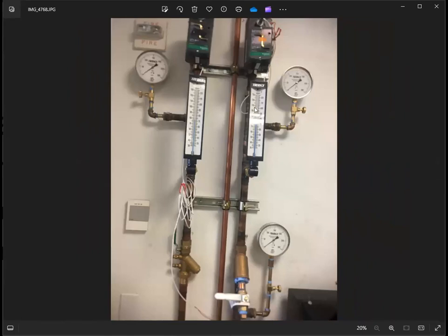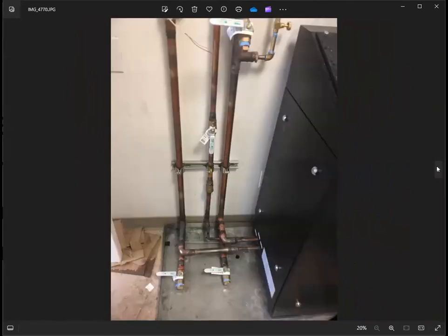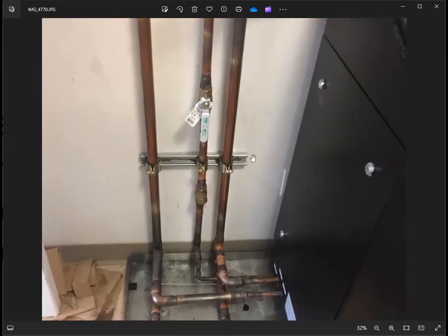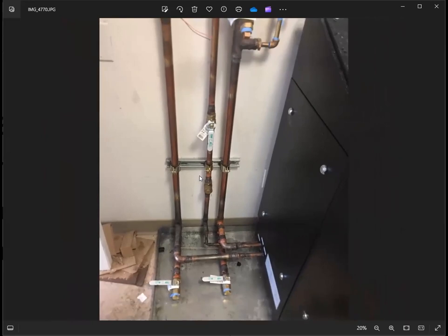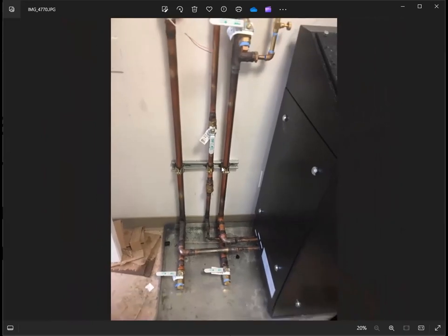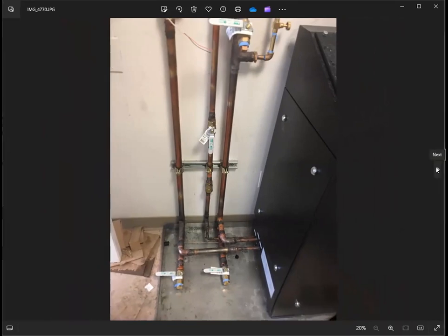Same. And this is the assembly for the gauges, pressure gauges. So this will indicate if your pipe has chilled water. So it's a chilled water unit. This is coming from the existing system, so they just branched it out to supply this equipment. So that's how they support. Take note of the support. It should be supported. The support is detailed on the drawing also or in the code. It should be every 5 feet vertically or 6 feet vertically minimum. It depends on the size of the pipe that you're supposed to support.